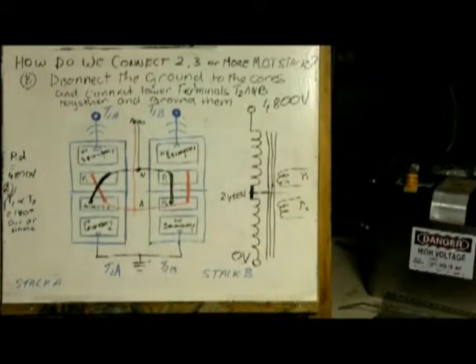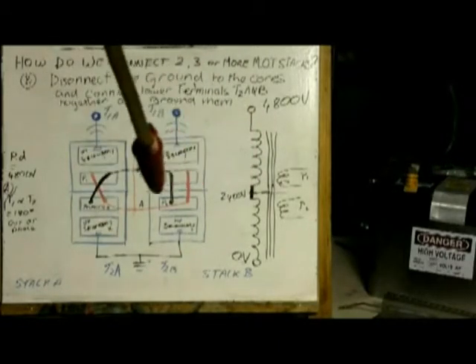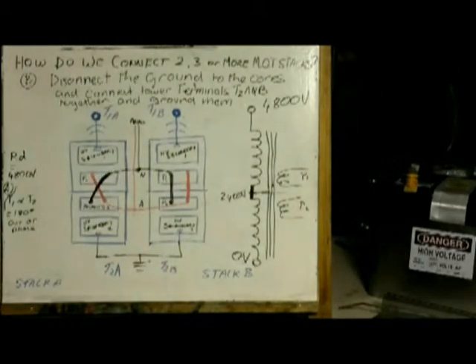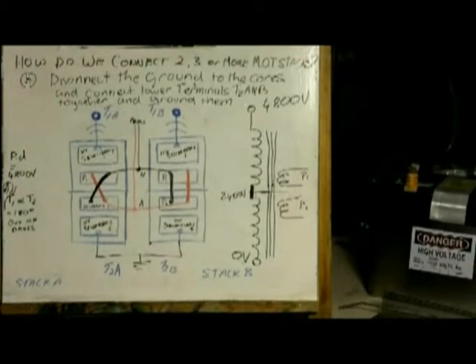So the second requirement, or requirement B, is disconnect the ground to the cores and connect the lower terminals 2, A and B, together and ground them. Okay? And remember, don't touch any part of this, don't touch the cores. They now have to be insulated from each other. You cannot connect the cores together either. Because right now the cores are at 2400 volts, you can't actually connect these two together either. So if you're thinking of connecting them together, it's not a good idea. I'll explain why that is in a minute.